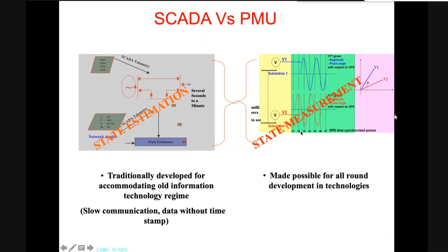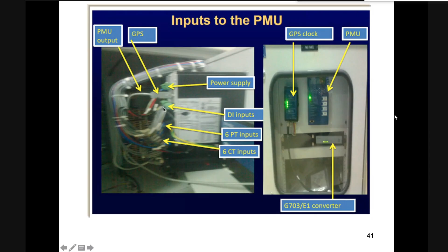Apart from that, it has inputs and outputs for measuring current and voltage. We can implement CT-PT, or otherwise a Hall sensor. CT-PT is a cost-effective solution, but a Hall effect sensor can measure both current and voltage with a single sensor, depending on whether you give analog or digital input. We also need a power supply to operate the system, and we have a GPS system. Whenever a fault occurs, the current and voltage values at that time are transmitted along with the latitude and longitude to the RLDC.